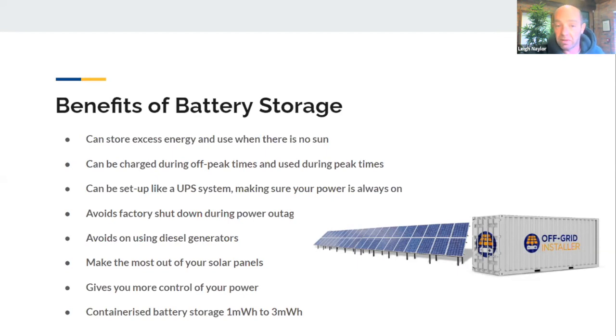A hybrid battery solar system can be set up as what's called a UPS system. You've probably got something very similar, but UPS stands for uninterruptible power supply, which means when the grid goes down, a static transfer switch switches across in milliseconds. You do not see a power cut - the batteries kick in and your power stays on without waiting for the generator to start up.